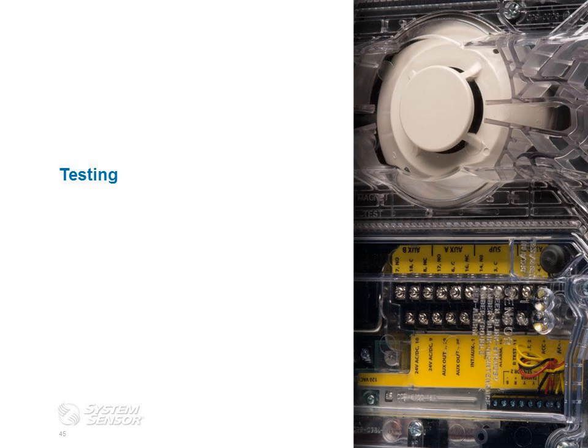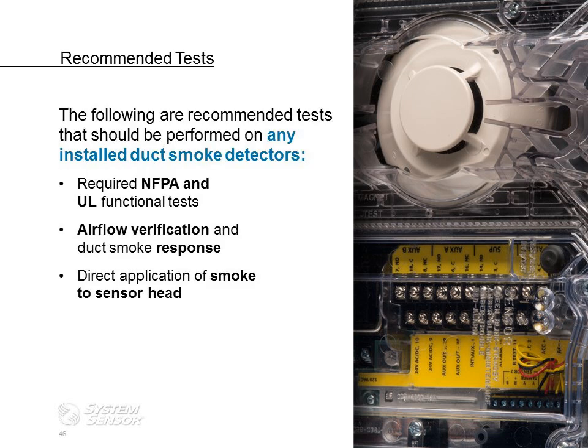The next section we'll talk about is testing. Recall that in the previous slides, we talked about how both the International Mechanical Code and NFPA 90A reference NFPA 72 for installation, testing, and maintenance. That's why this is important. The following that we're going to talk about are recommended tests that should be performed on any installed duct smoke detectors, regardless of the make and manufacturer. There are certain required tests. Those are NFPA and UL functional tests. We also recommend that for every duct detector that's installed or serviced, you do an airflow verification test to make sure that it's installed properly. And then there's also a direct application of smoke to a sensor head test.